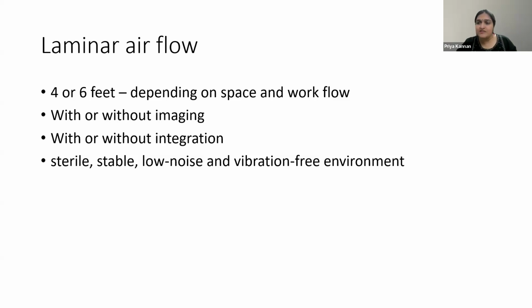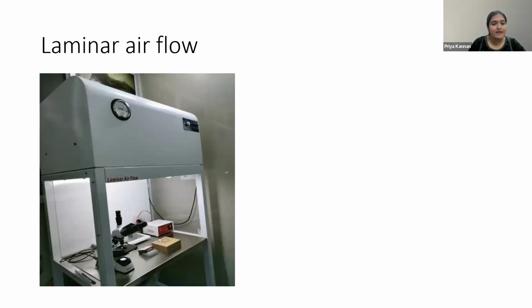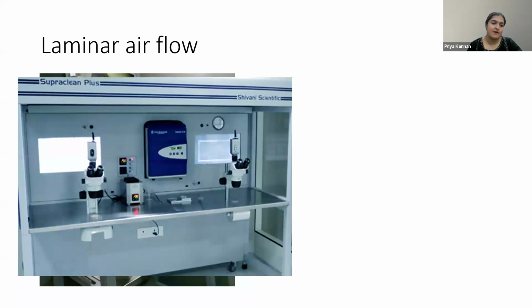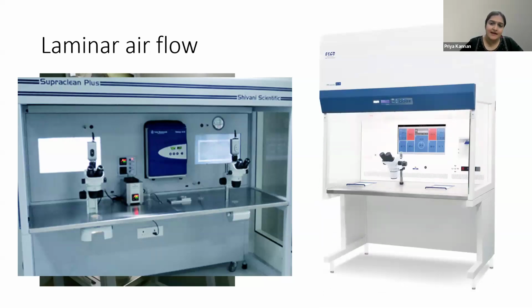But what is the purpose of laminar airflow? It is to have a sterile, stable, low noise and vibration-free environment for the manipulation of the gametes and the embryos. So that is one type of laminar airflow, which does not obviously have the integrated stage, because as you see, the microscope is set as such right inside the laminar airflow. And here is the integrated laminar airflow, where you can see two microscopes that have been fit in here. It also has a small incubator, an imaging system and a test tube warmer. Here is another type of integrated laminar airflow, where you can see one stereozoom microscope with imaging system.